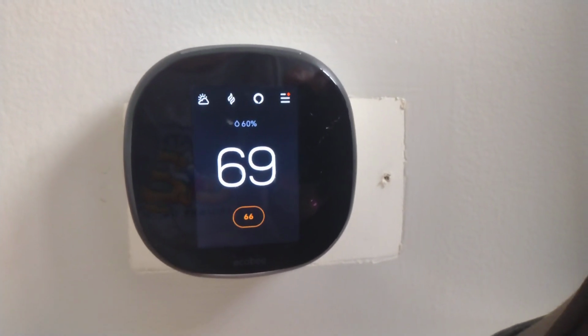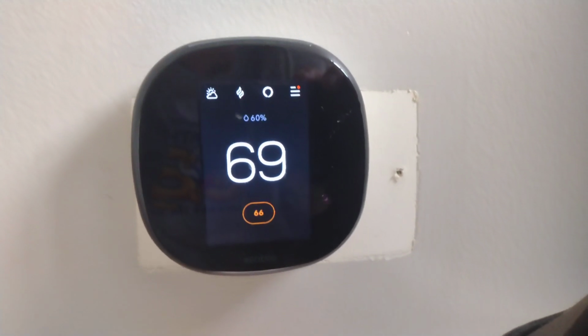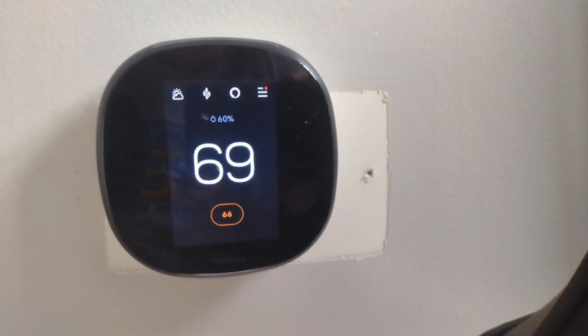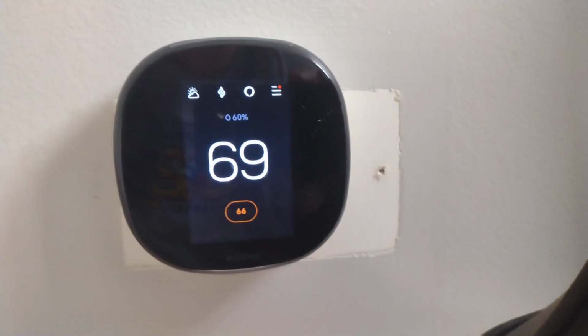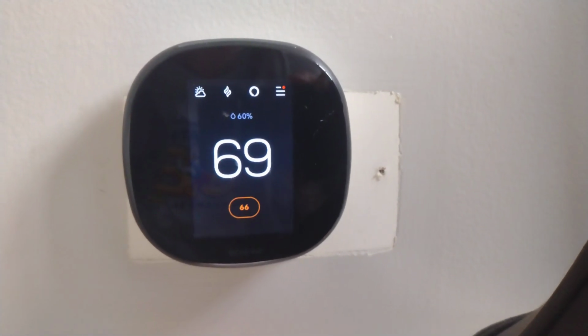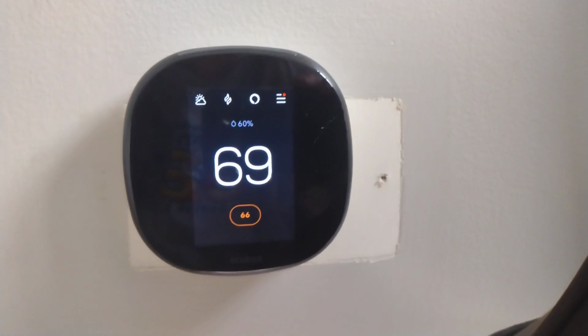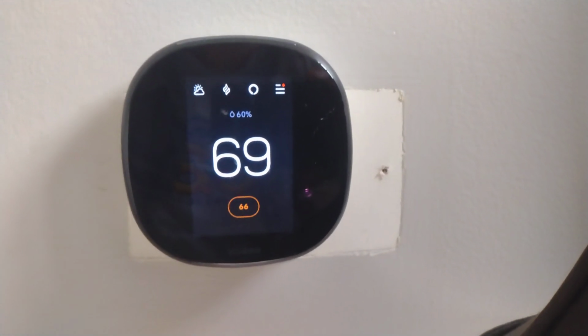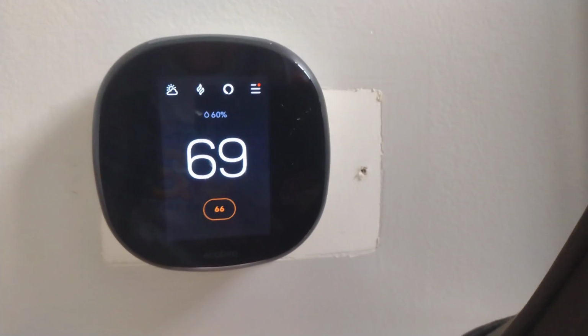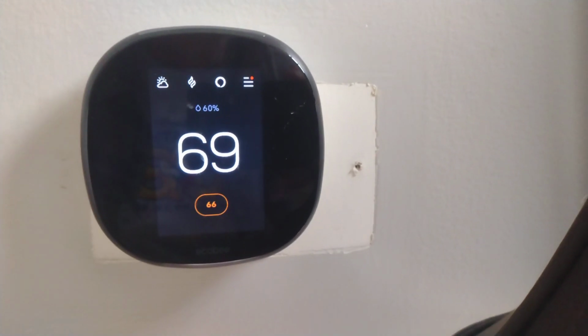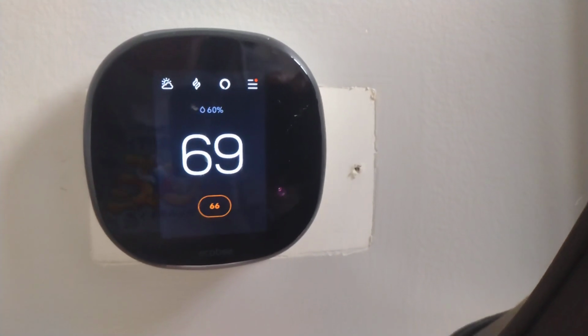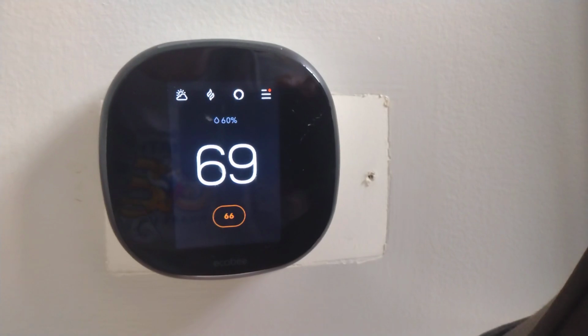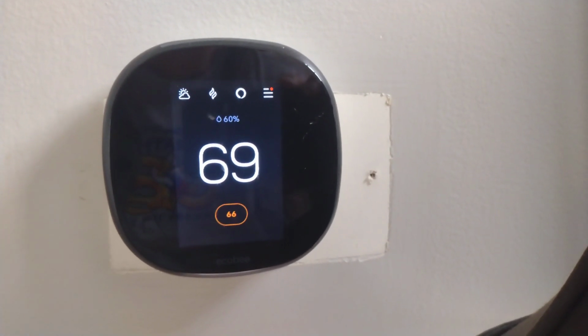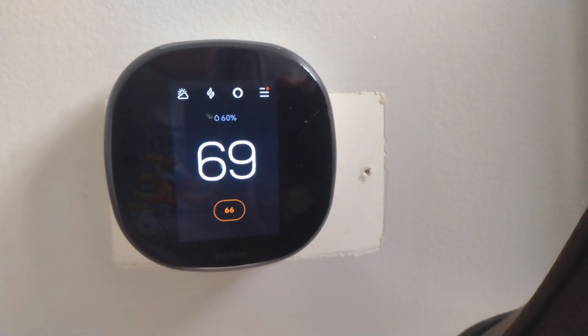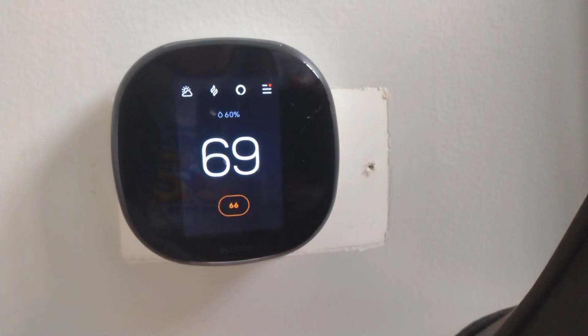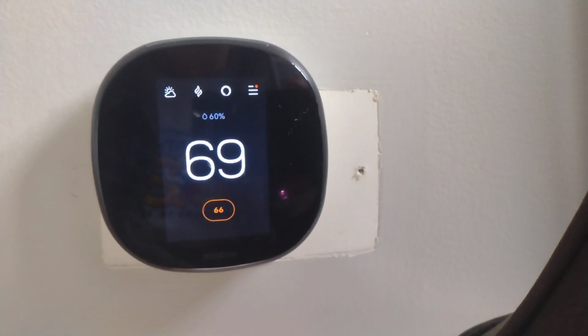So if you have intermittent power issues with your Ecobee, that's likely what the problem is. We've had that happen on 2 units in about the same amount of time, a year or two difference. And upgrading or just replacing the low voltage transformer on both air handler and furnace has seemed to solve the problem. We haven't had any intermittent power issues since we took those measures.